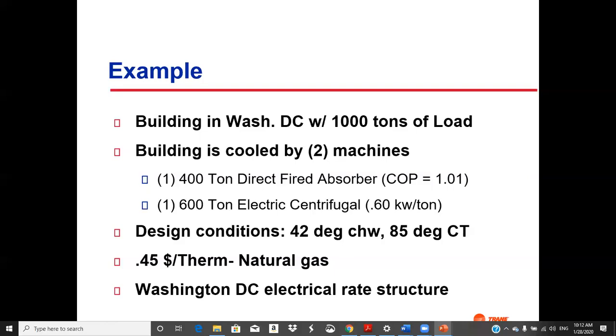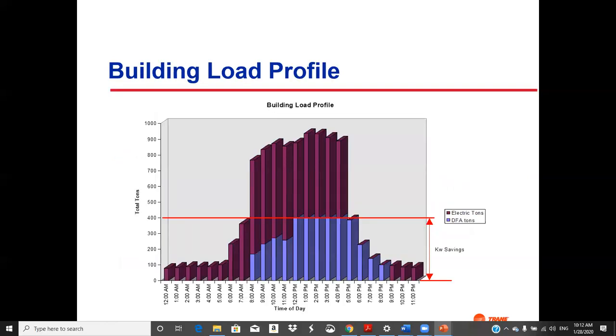There's our cost and DC electrical rate structure. So there's the building profile. We're seeing the electrical is providing this portion, and the direct fired absorption is the brighter blue. This kind of shows you when this on-peak period must be, because that's when they're operating it, from 8 a.m. to 8 p.m. So they've got a 12-hour on-peak window. As this comes up, the breakdown between the loads, I'm not sure. Well, this may be the on-peak here, because this is where they're maxing out the absorber. I'm not real sure. They don't give a very good explanation in here.